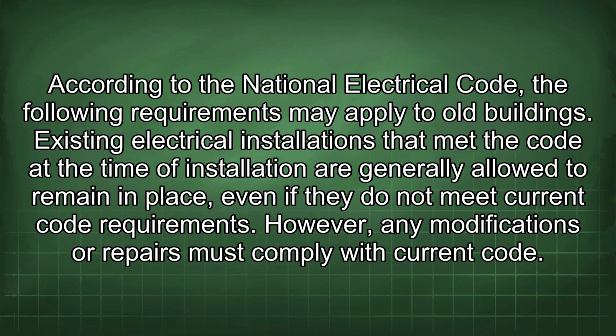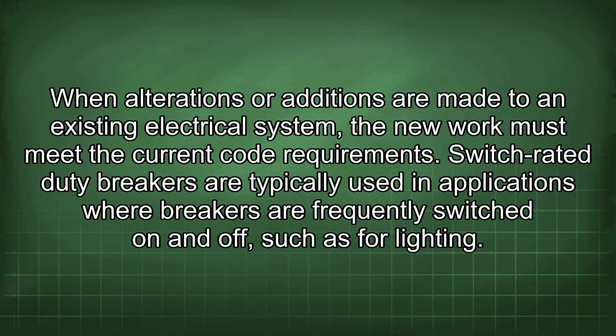According to the National Electrical Code, the following requirements may apply to old buildings. Existing electrical installations that met the code at the time of installation are generally allowed to remain in place, even if they do not meet current code requirements. However, any modifications or repairs must comply with current code. When alterations or additions are made to an existing electrical system, the new work must meet the current code requirements.